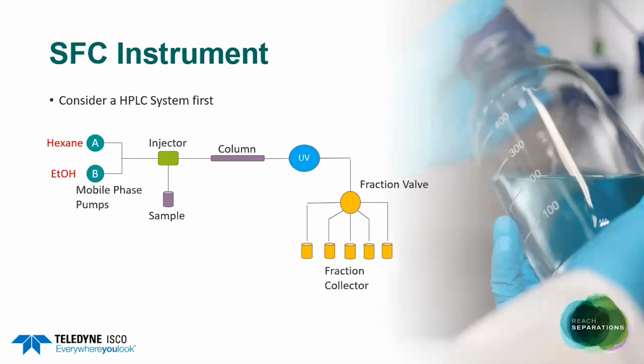If we move on to an SFC instrument, to just give you a brief outline of what one will look like, we'll consider an HPLC system first. So over on the left, at the start of the system, we can have one mobile phase pump and pre-mix our solvents, or we can have two pumps and mix online. Then we have the injection system to introduce our sample into the flow path. And in this example, we have the total mobile phase flow going through the injection system. Following this, you have the column, and then the detection means, which in this case is UV. And then lastly, we have the fractionation valve with the collection vessels.